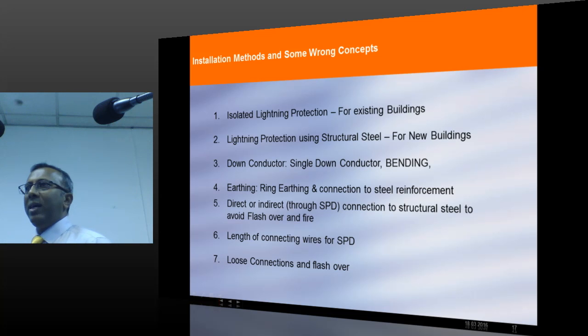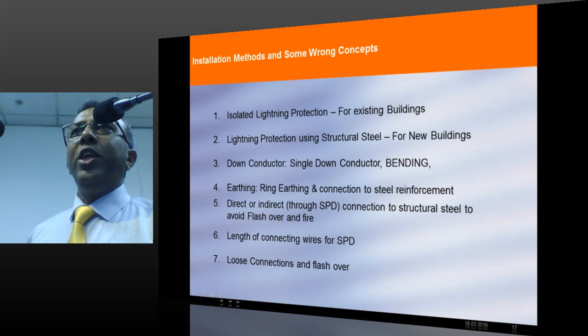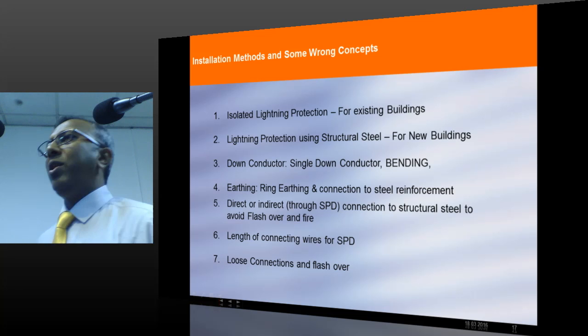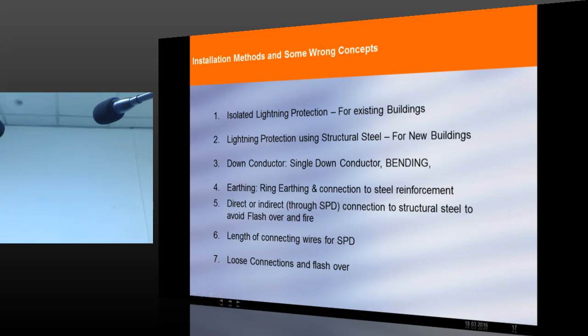Also, when we talk about earthing, the knowledge of ring earthing as well as the knowledge of using foundation earthing is missing in some parts of Asia. In some places, if we say you have to make a foundation earthing, then the argument starts. No, my structural engineer will not allow connecting the reinforcement to my down conductor or earthing. Because what people believe is, if you have a down conductor, maybe 2 down conductors, isolated and away from the building, then the current flows. So my structural engineer will not allow integrating the lightning protection into the structural steel. This is also a big argument.